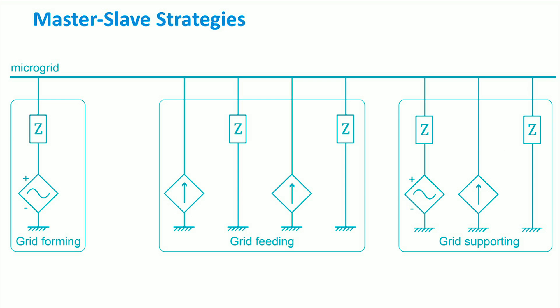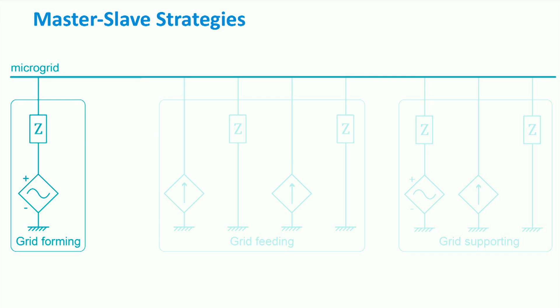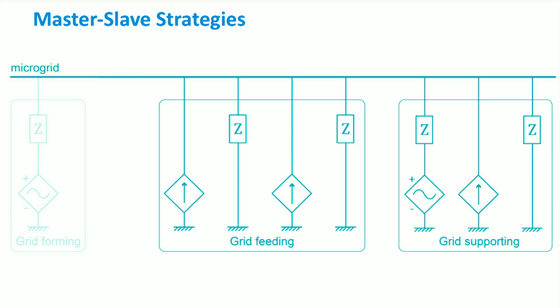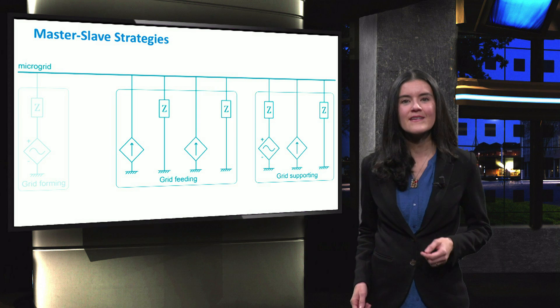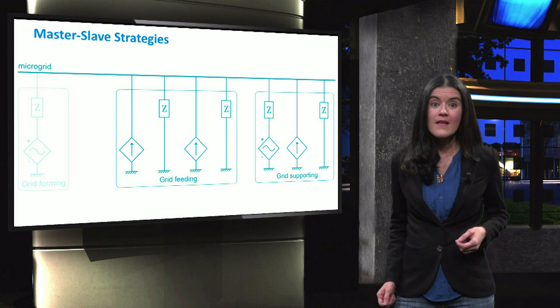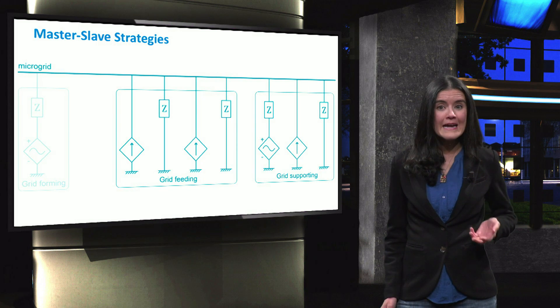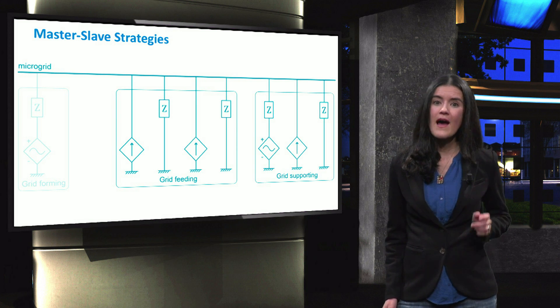The master-slave control strategy is a mature solution for the parallel operation of several distributed generations in microgrids. The master unit is represented by a grid-forming type, which dominantly controls the voltage and frequency of a microgrid. Grid feeding units, called slaves, mainly follow the voltage and frequency imposed by the master unit, while trying to follow their active and reactive power setpoints. Moreover, both types of grid-supporting units can be connected to such microgrid in a flexible way. In any case, a supervisory control is needed to appropriately divide the power among all the units. The main advantages of the master-slave control strategy are its simplicity, being quite straightforward to implement, and its robustness.